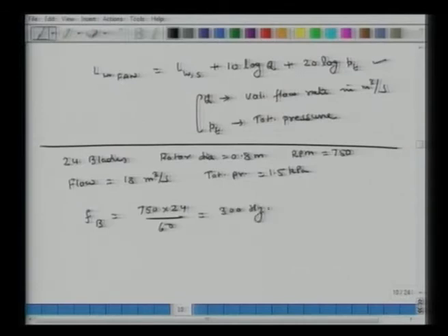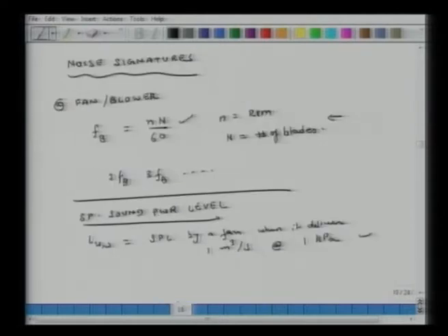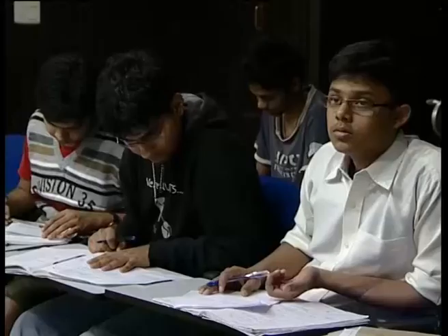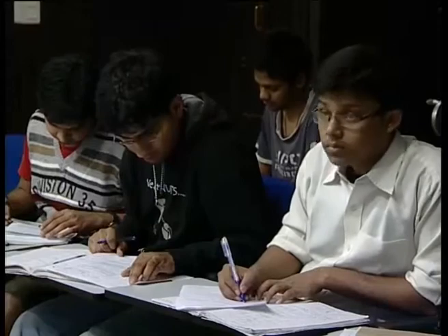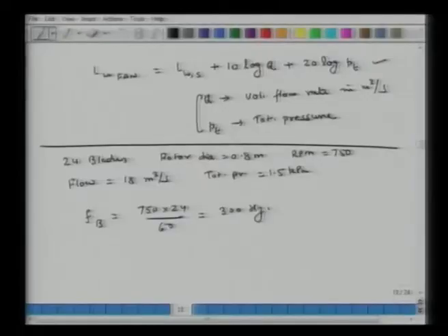What is LWS for this fan? A specific sound power level? This fan is radial curved forward. So, in the table, if you look at forward curved fan, what is the LWS? Which row should I pick? The last one, right? Forward, 98 98 88 81 81, that row, right? Does everyone see that? So what I'll just do is very quickly develop a matrix.